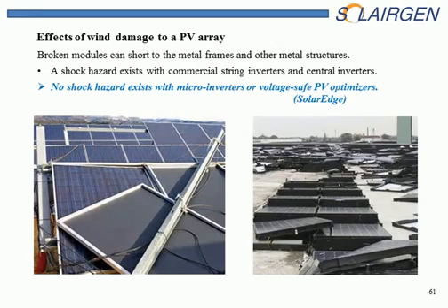Wind damage can create a hazardous situation on a roof. This is a commercial installation, both of these pictures are, and the modules are tossed about. Some of them are broken, and that means that there's a good possibility that the DC power is shorted to the frame of the module, which means everything metal that's connected to this PV array potentially is energized. So that's the big caution if you're working on a system that has damaged PV modules on top of a roof, there could be live power up there.